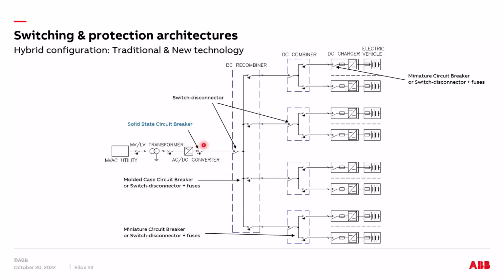The second architecture is a sort of hybrid architecture where we have a main so-called solid-state circuit breaker. This is a new technology of circuit breaker, and we have just developed this type of circuit breaker. This circuit breaker is very, very fast. So in case of a short circuit at every point of this architecture, this circuit breaker is able to detect the short circuit contribution coming from the DC capacitor discharge and from the DC grid. This means that it is able to reduce the current peak coming from the DC capacitor, and also to protect the internal freewheeling diodes of the converter.